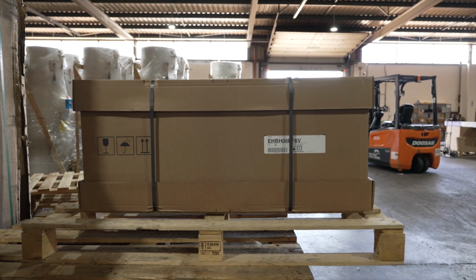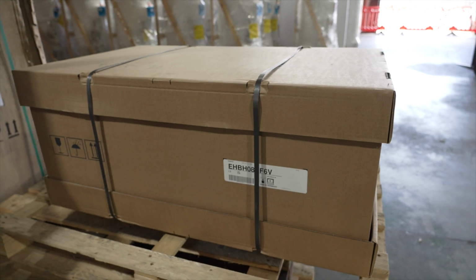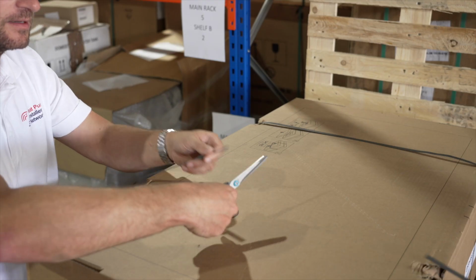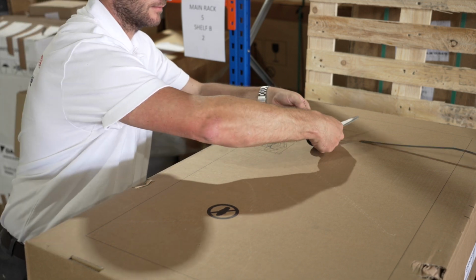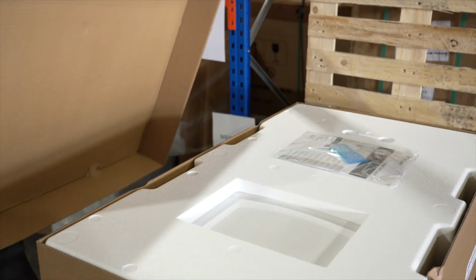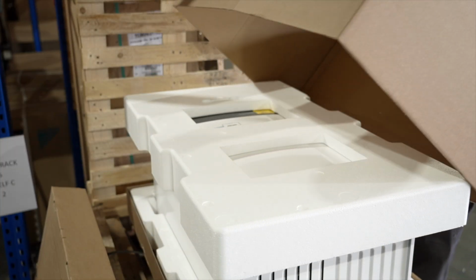The Hydrobox is part of a hydrosplit system and is connected to the high temperature outdoor unit. When you unbox the Hydrobox, do not cut the box open to get in. The unit itself has very little in the way of protection and is easily damaged if you use a Stanley knife to open it up. Cut the straps on the side of the box and the lid will lift off, and then the sides of the box can be removed.